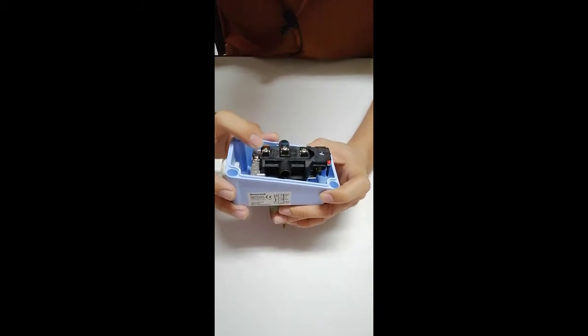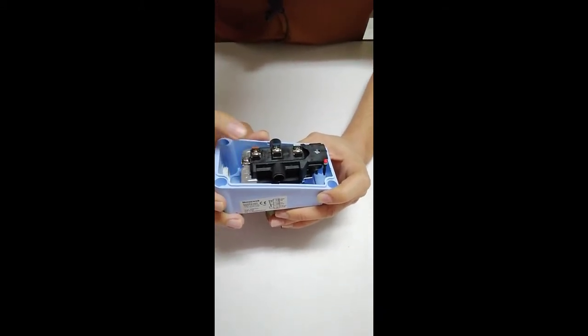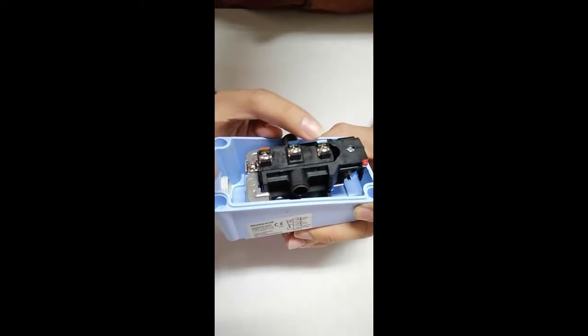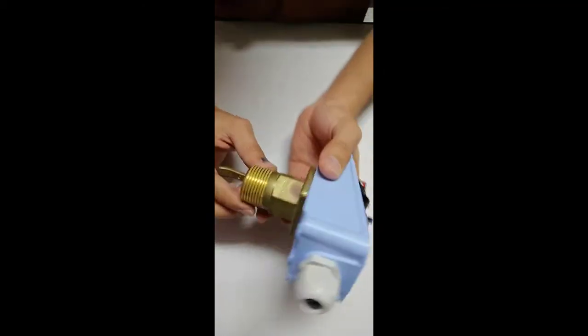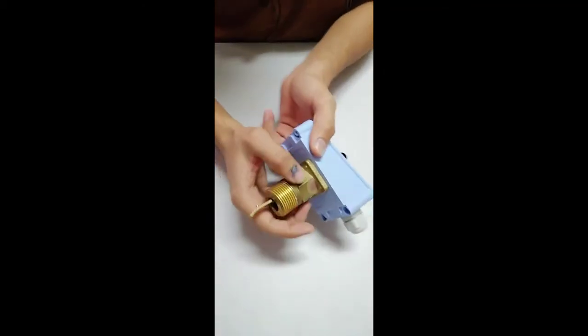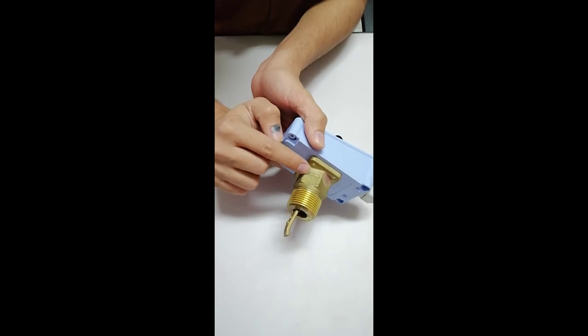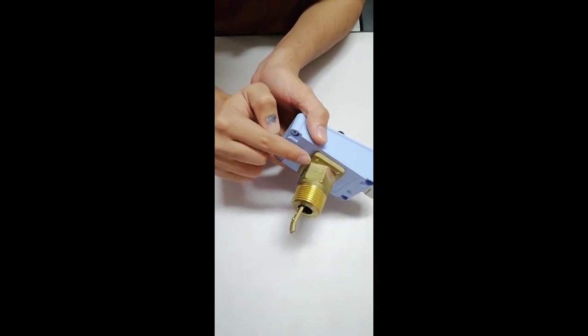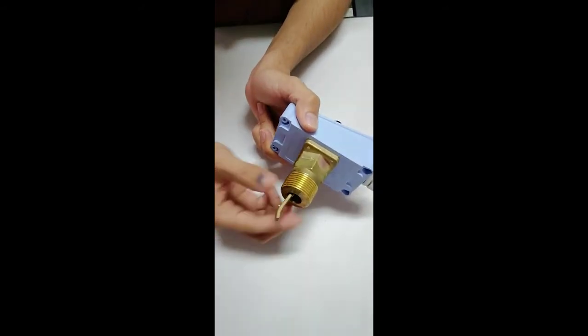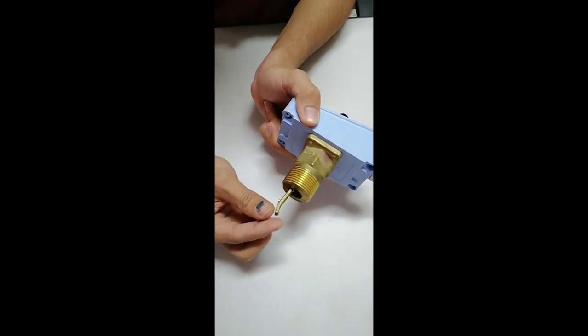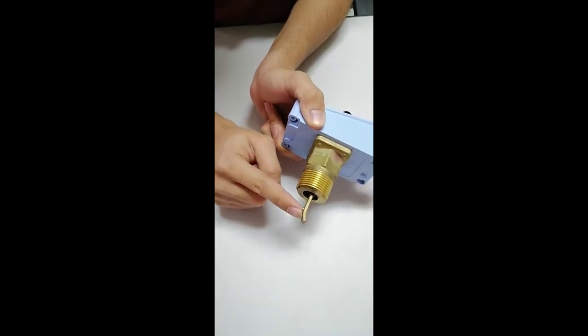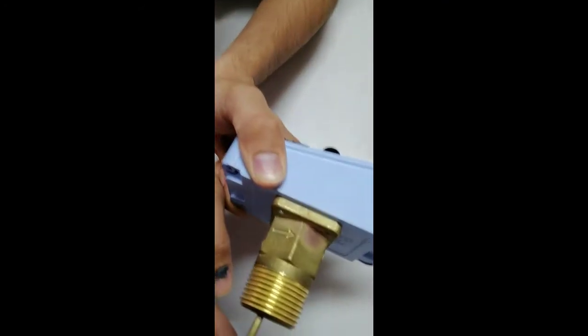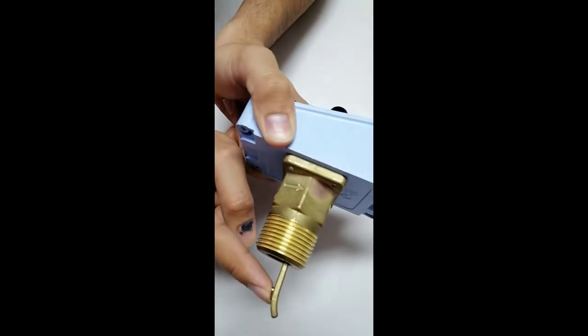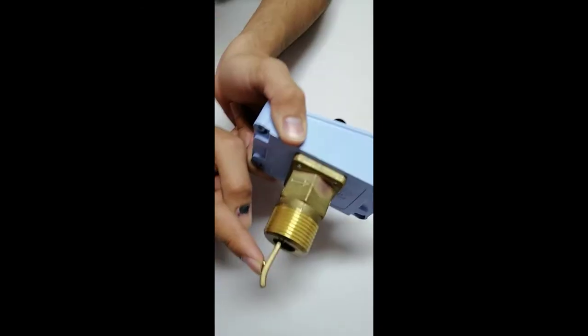Here we have contact points. This is common, number two is normally open, and number three is normally closed. On this flow switch we have an arrow, which shows the flow direction of the water. It is directly installed on the pipe. When we detect the flow, this probe moves and we get this signal, as you can hear. So this is how we detect the flow.